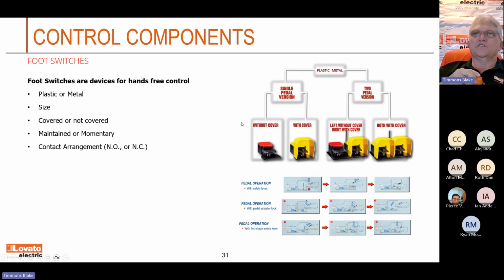Okay. Foot switches, that's another control device out there, and these have different things to look for. I think this little breakdown I found on the slide is really nice. These are just our plastic ones, but you can do a single pedal, you can do a double pedal, you can do them covered, not covered. You have them with a safety lever. You have them that'll latch on a double tap. And then of course the contacts. You're still going to be looking for how many normally open and normally closed, maintain or momentary.